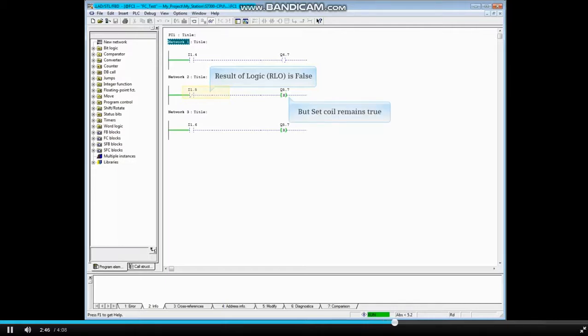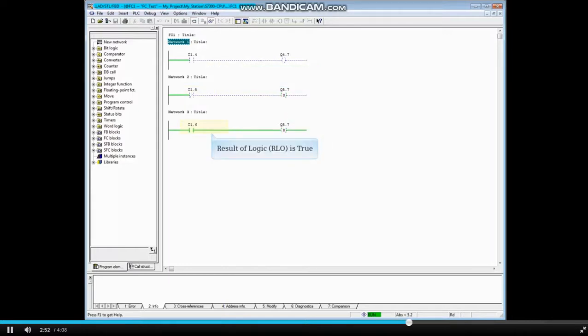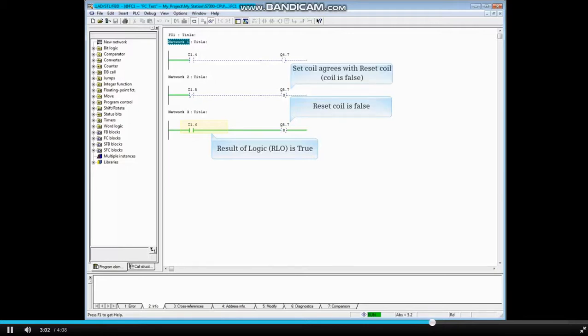The set coil remains true. The reset coil agrees with the set coil and is also true. Input I 1.6 has been turned on and the result of that logic is true, which resets output Q 5.7 and the coil goes false. The set coil agrees with the reset coil and is also false.